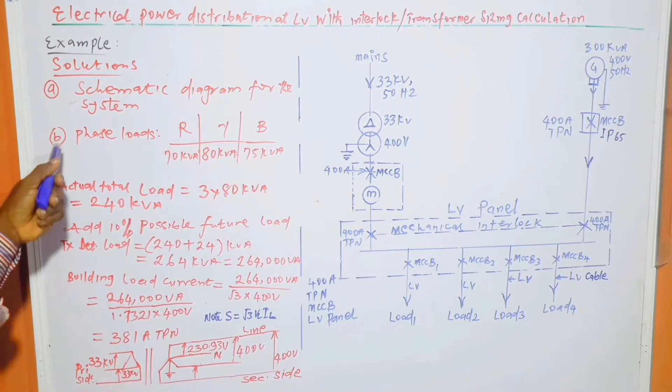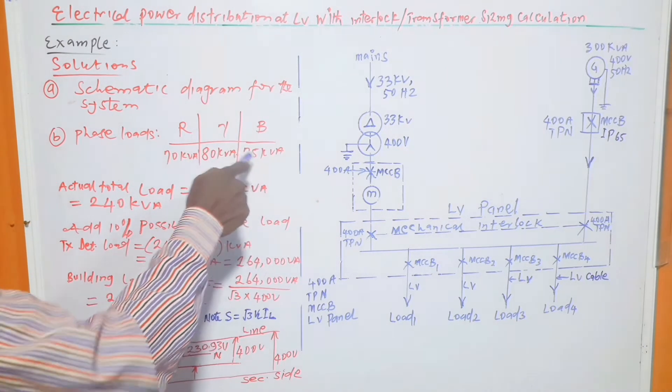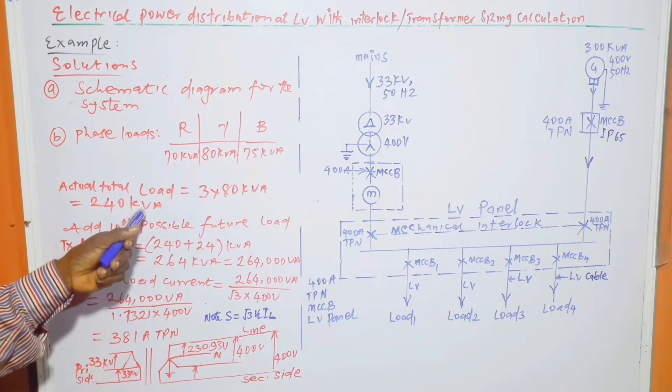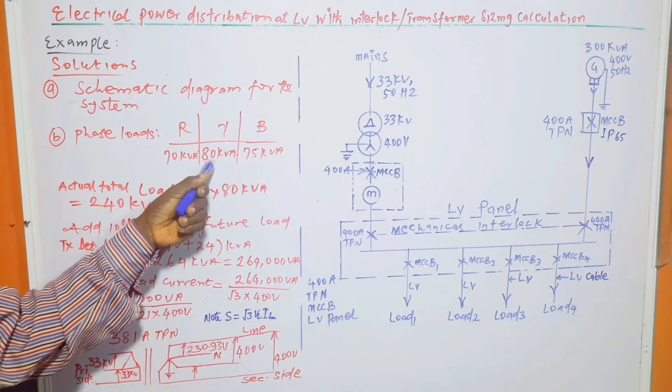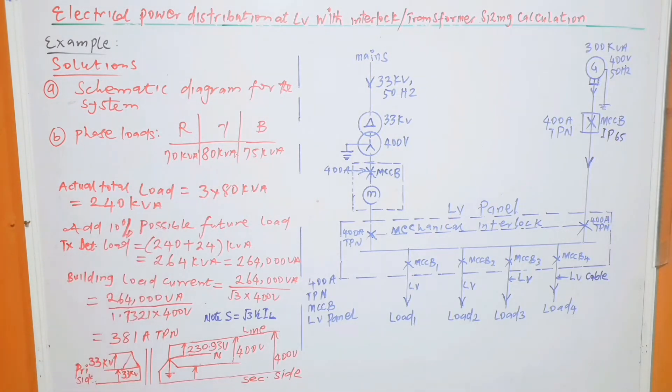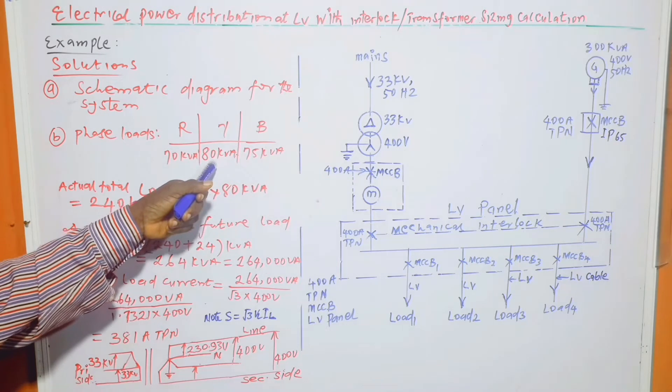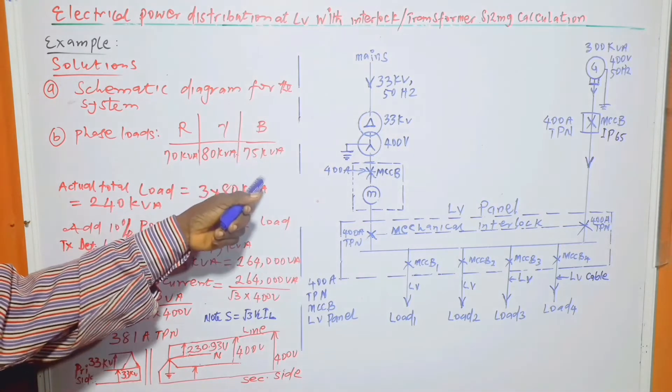Part B: Phase load - red phase 70 kVA, yellow phase 80 kVA, blue phase 75 kVA. Actual load is equal to 3 times 80 kVA, which is equal to 240 kVA. This 80 kVA is the highest phase load, as I explained in one of my previous videos having to do with transformer load calculation slash transformer size calculation. In this situation, you will multiply 3 by the highest phase load, which is 80 kVA. You shouldn't add the algebraic sum of the phase loads.